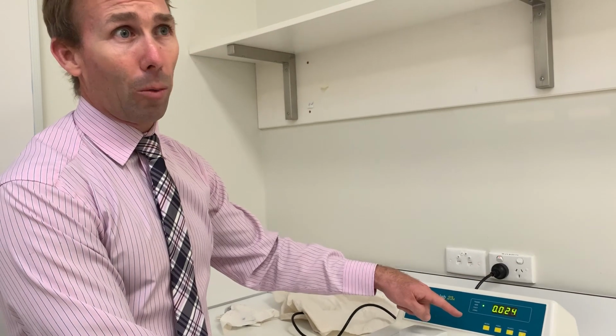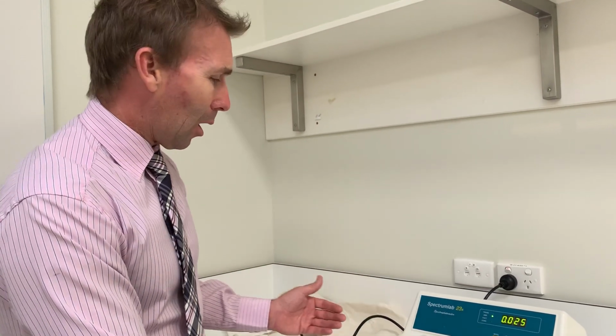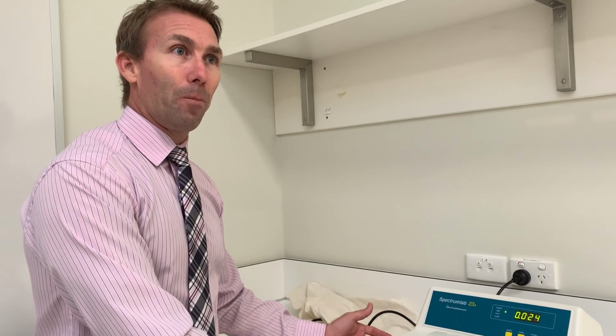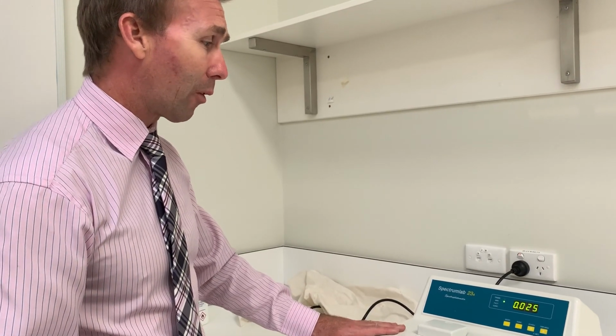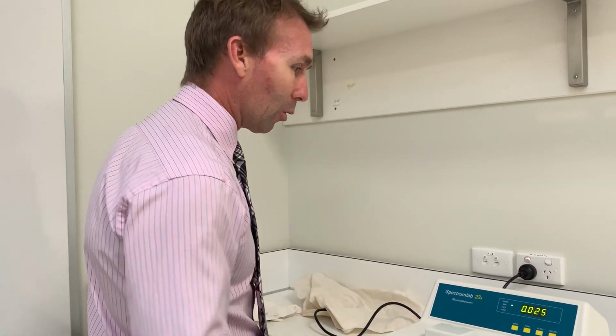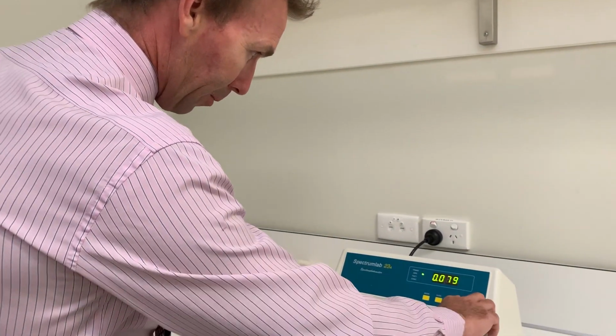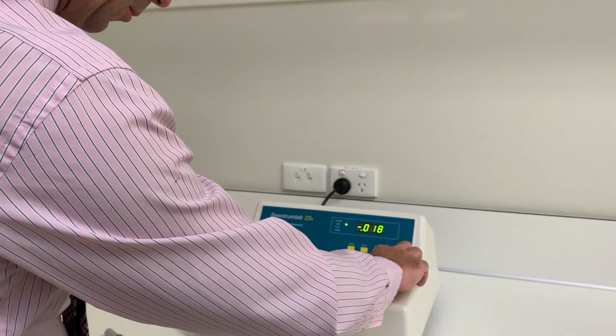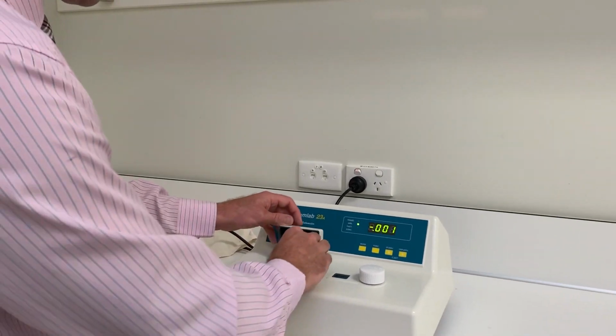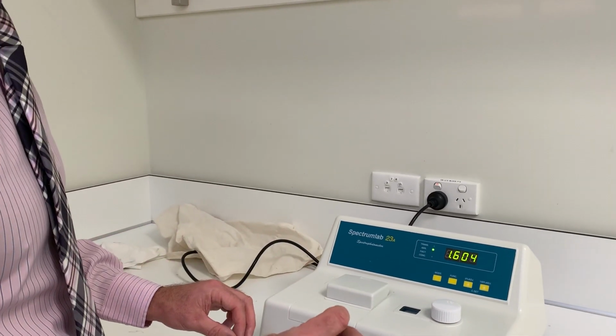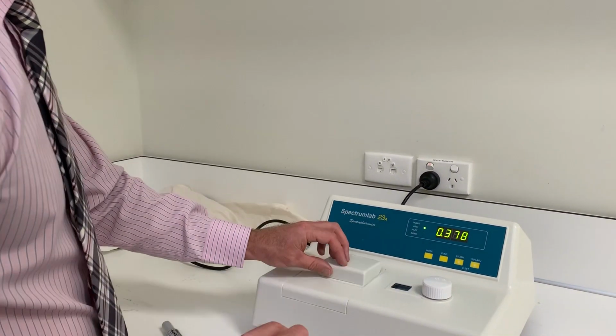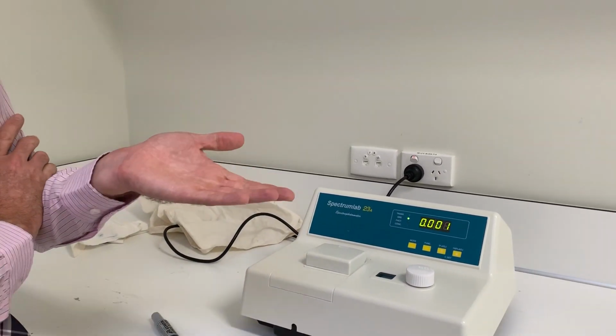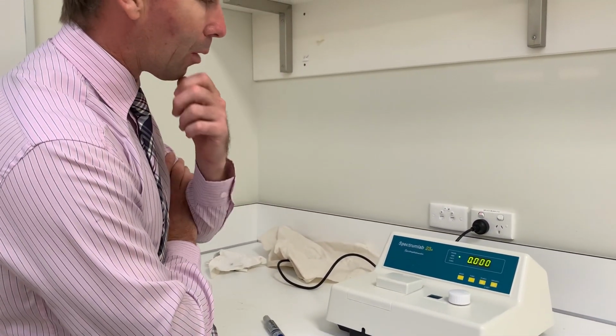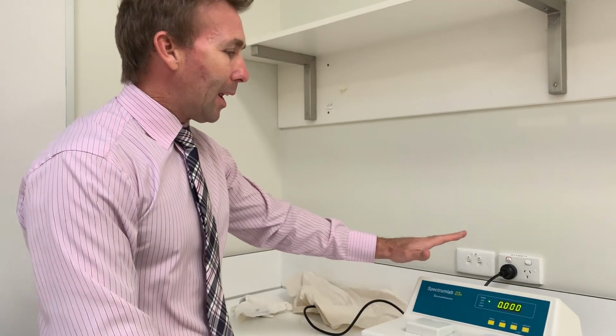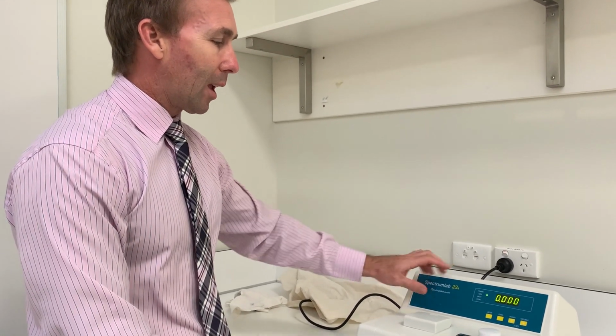So logic tells you that should have gone back down to 0, but it hasn't gone back to 0. And I think the reason for that is that the monochromatic light source is still warming up, so we're still getting variation in those readings. So that kind of stresses the importance of warming up the monochromatic light source. But if that was the case, let's press 100% adjust again. There we go, we've got it back to 0. Let's just see now if we put it back in. Pretty good. Okay, so that's pretty close to 0 there. Back to 0.